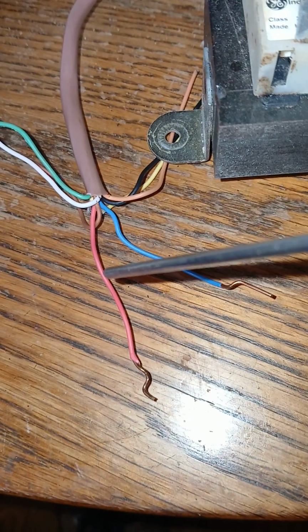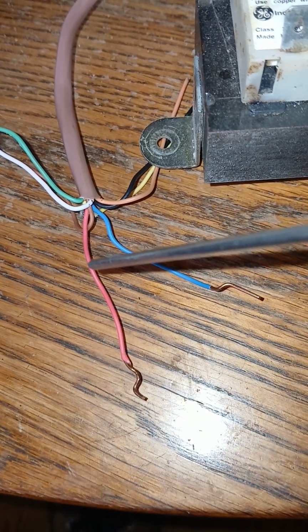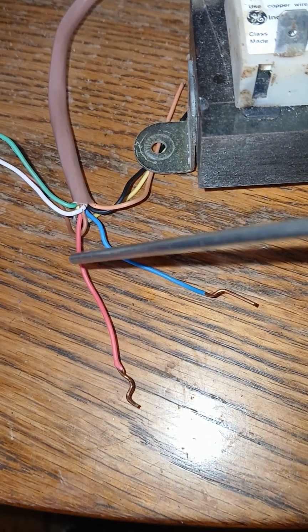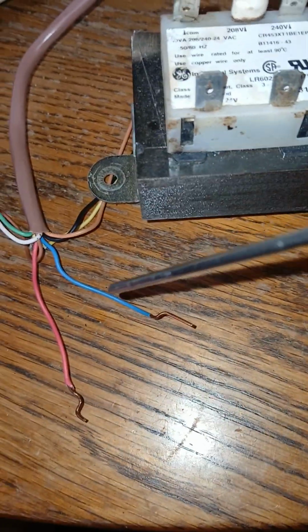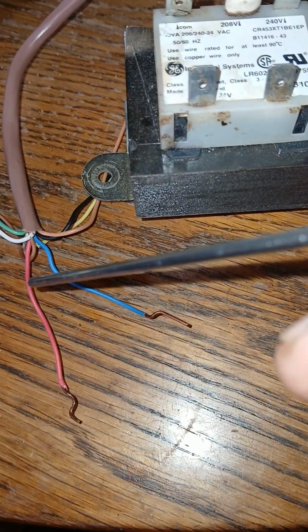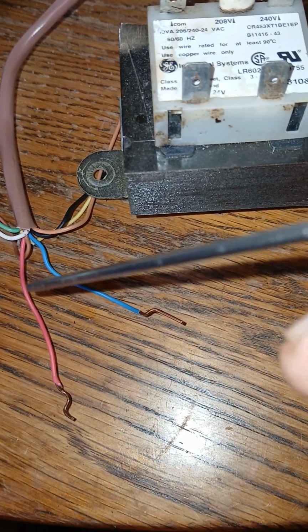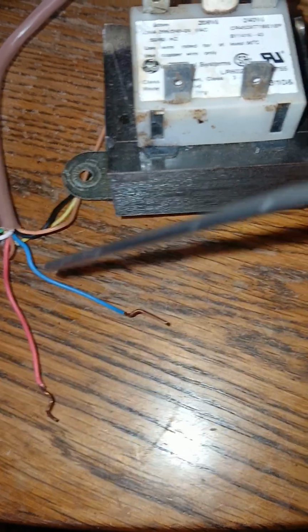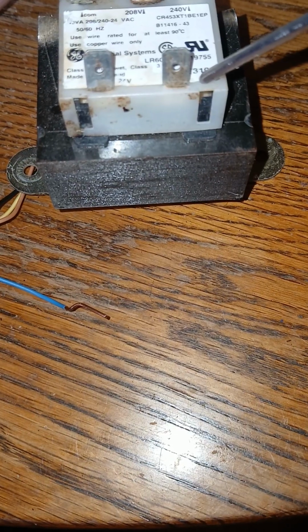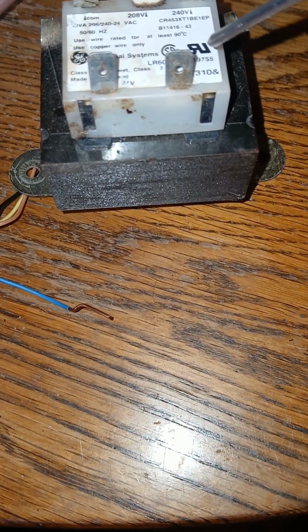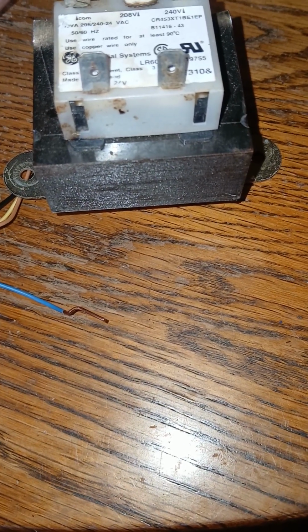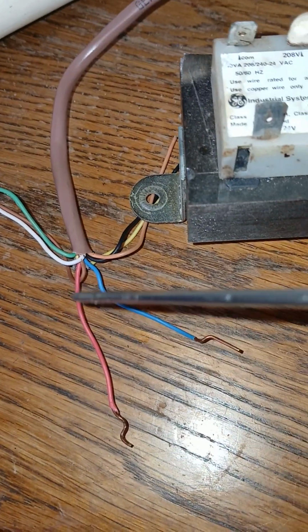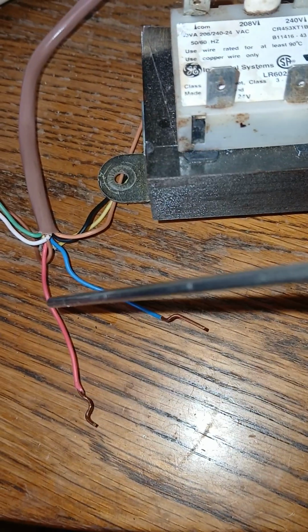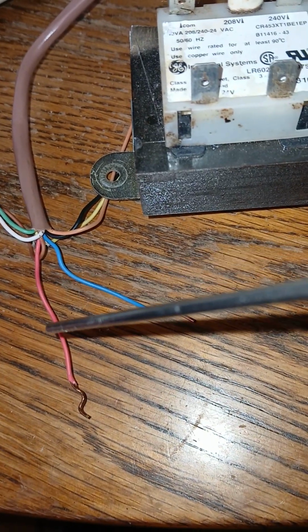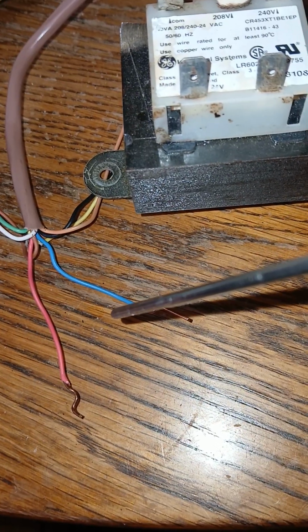But now if you have a fuse, an inline fuse in the red wire here, this could protect you. I'm not certain if it would throw the fuse, but it may throw the fuse, and if it threw the fuse, it would protect the transformer. So my opinion is it may not be a bad idea to have an inline fuse on the hot side, the red side, and then the blue side would be the common wire.